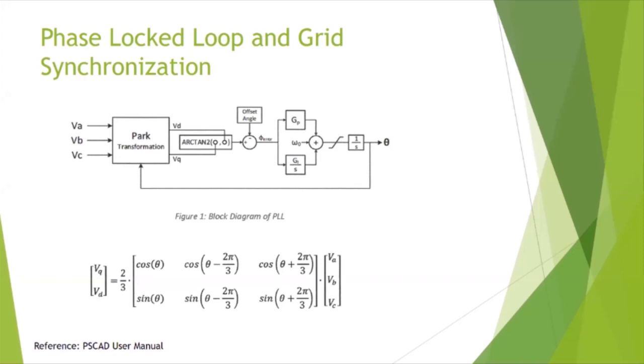Something very important is making sure the phase lock loop is stable under the operating conditions of the solar power plant. For that, you have to tune the proportional and integral gains, and this is actually a very challenging task, especially when the solar power plant is connected to a weak grid.